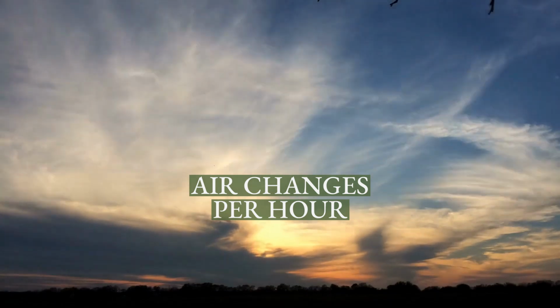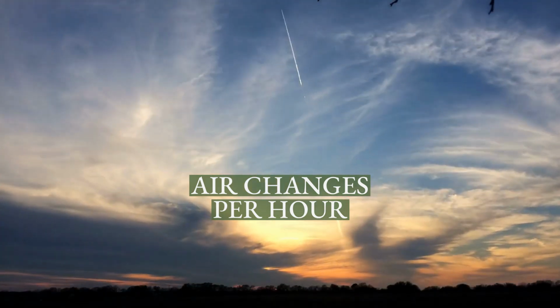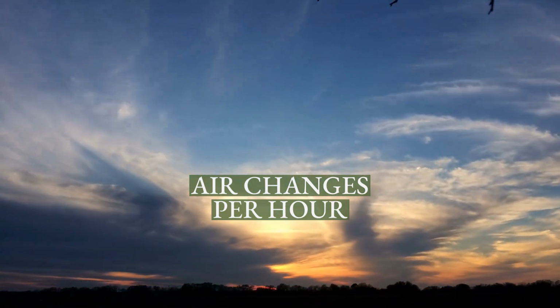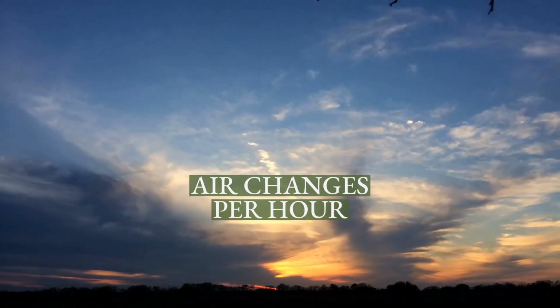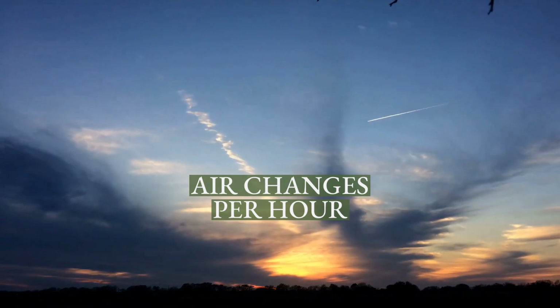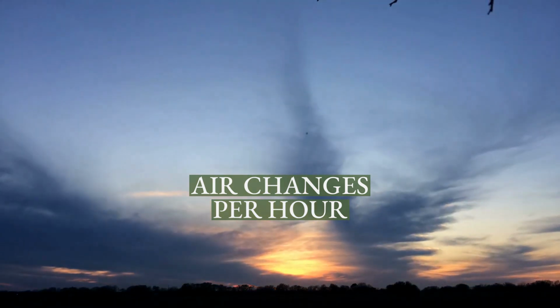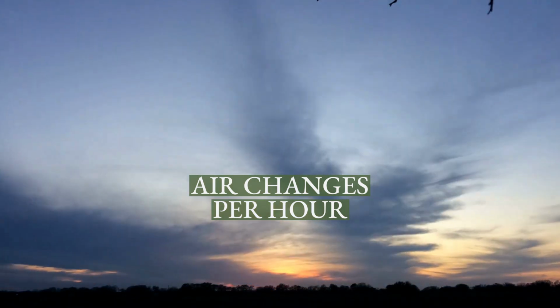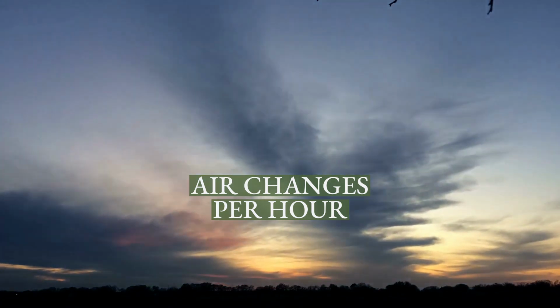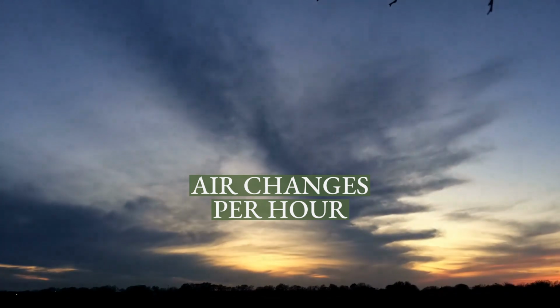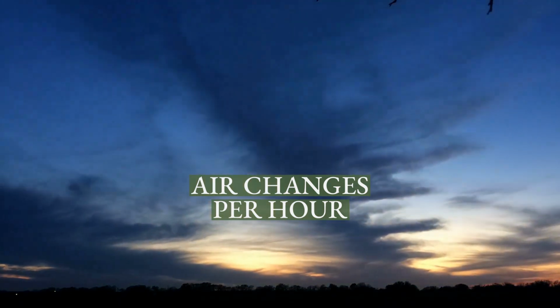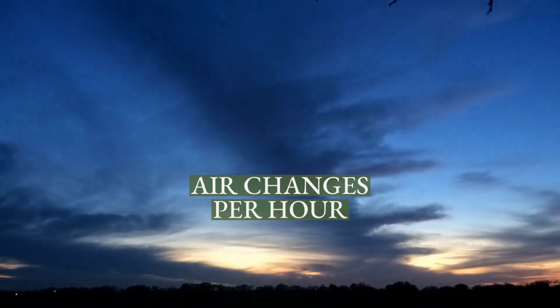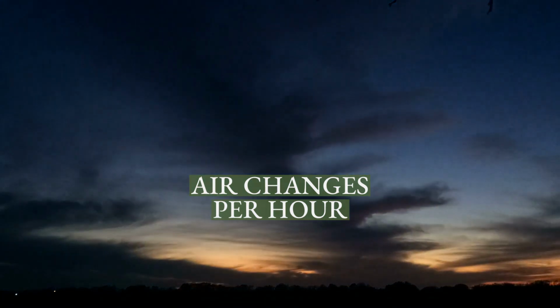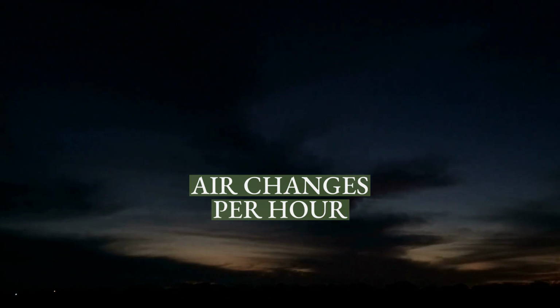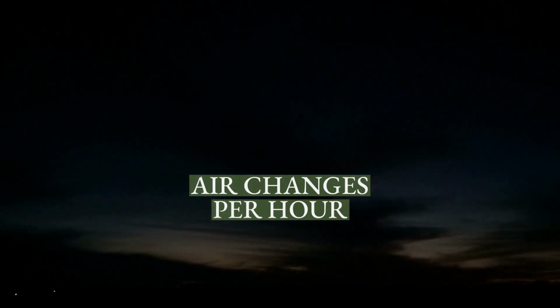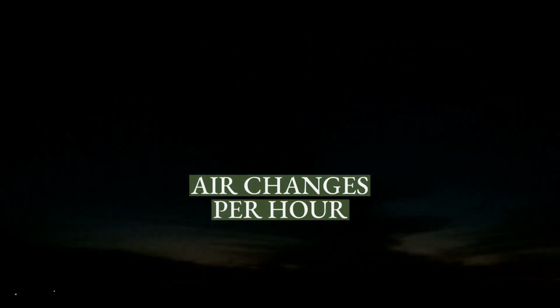These systems range from a conceptual system of perfect displacement, which removes and replaces all air in a space, to a short-circuit flow in which very little of the existing air is replaced. The actual amount of air change in a well-mixed ventilation scenario will be 63.2% after 1 hour at 1 ACH. In order to achieve equilibrium pressure, the amount of return air leaving the space and the amount of supply air entering the space must be the same.